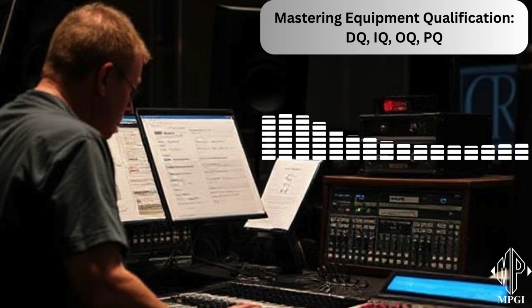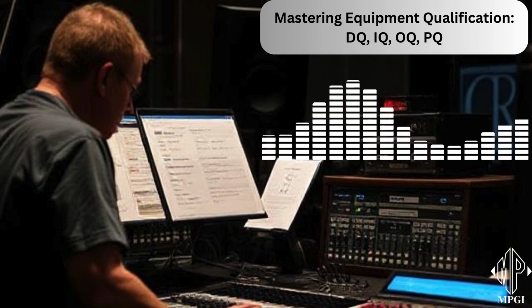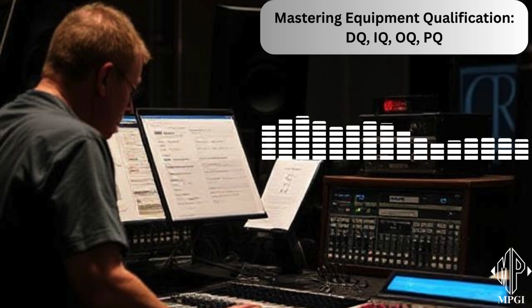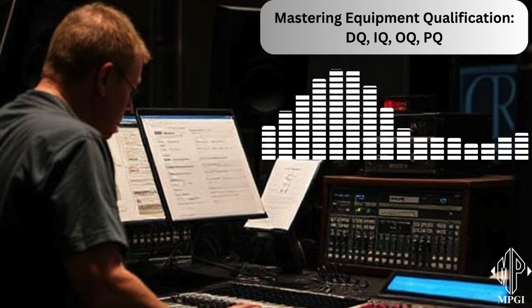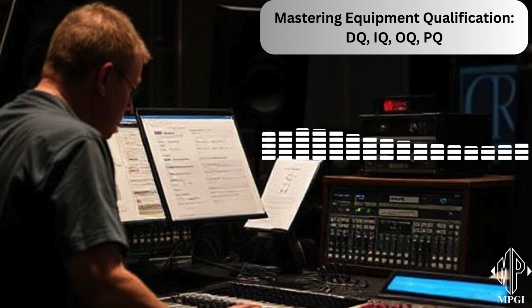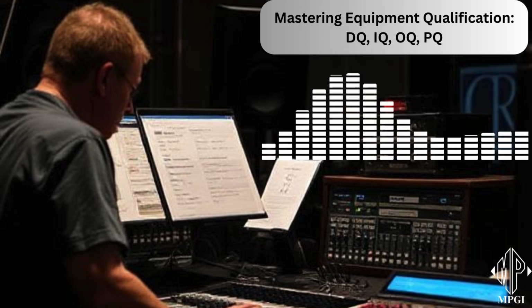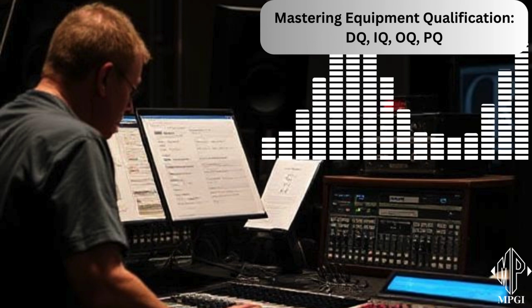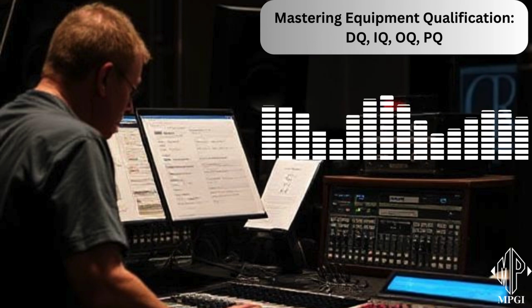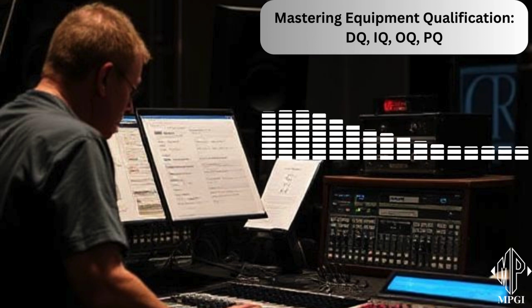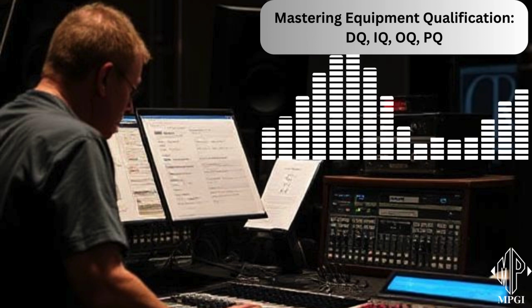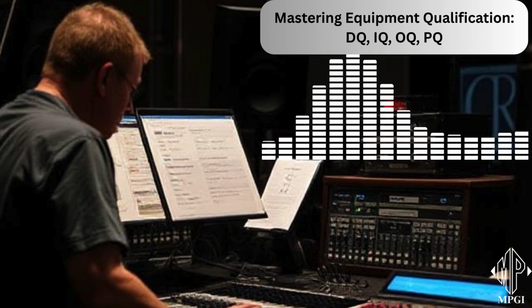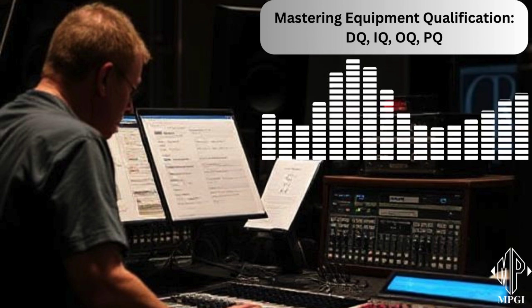Exactly. And finally, you talked about change control. What role does that play in maintaining the qualified state? Change control is all about managing any changes to the equipment, software, or processes in a controlled way. Any change has to be evaluated, documented, and approved before it's implemented. This includes assessing the potential impact on the equipment's qualified status and deciding if any requalification or additional testing is needed. It's all about making sure changes don't accidentally undermine the qualified state.